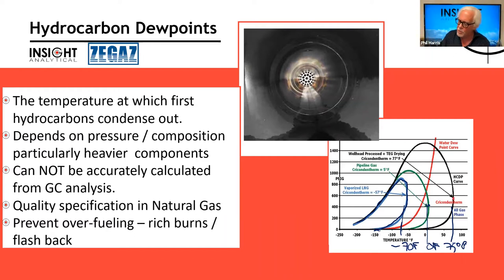Again, it's an important quality specification on natural gas. Too much hydrocarbons, the potential for liquid hydrocarbons, can, in a burner, whether it's a home furnace or a combustion unit, cause flashbacks, cause flameouts in burners, and overheat gas turbines. So there's a bunch of issues that potentially occur when we have too many heavy hydrocarbons in our system. And so the important specification then becomes: what is my hydrocarbon dew point? Gas transportation companies realize that managing hydrocarbon dew points reduces a lot of their liabilities and opens up other gas markets for their products, generating more operating revenue.